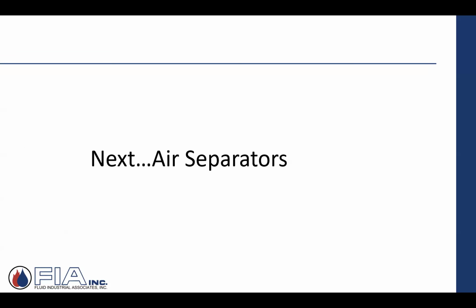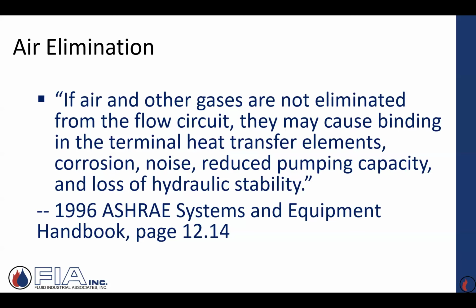Moving away from pumps for a second, getting into what we'd call air separators, another component that's very important in the hydronic system, both heating and cooling, but especially heating, but it has its place in the chilled water world as well. So just a statement out of an older ASHRAE systems and equipment handbook. If air and other gases are not eliminated from the flow circuit, they may cause binding in terminal heat transfer elements, so fan coils or what have you. Corrosion, certainly noise, it'll create a noise factor that would be objectionable.